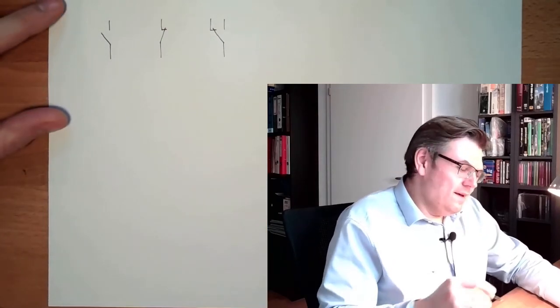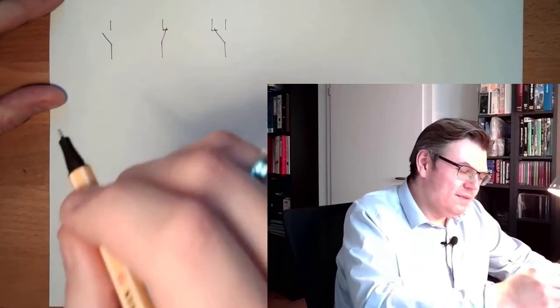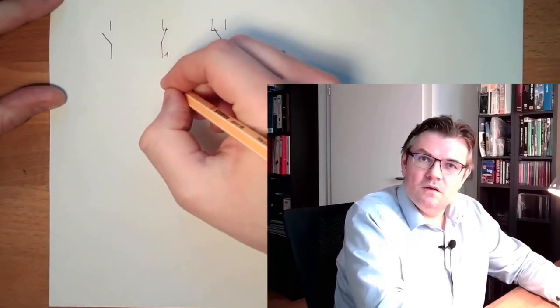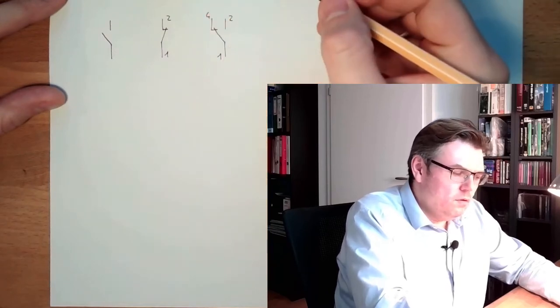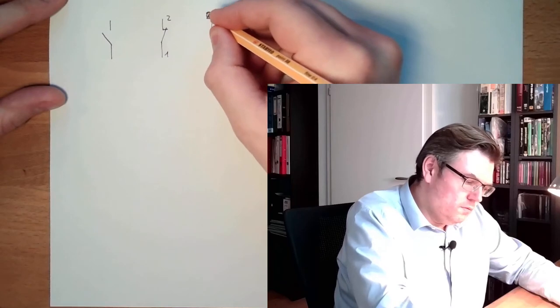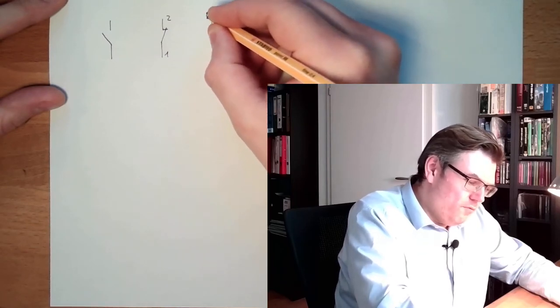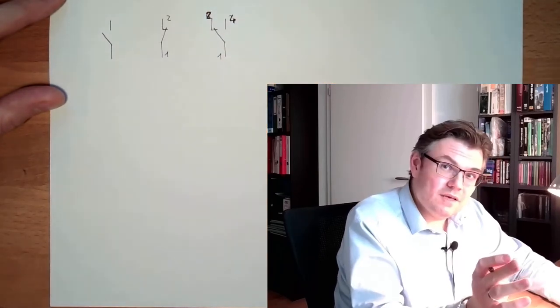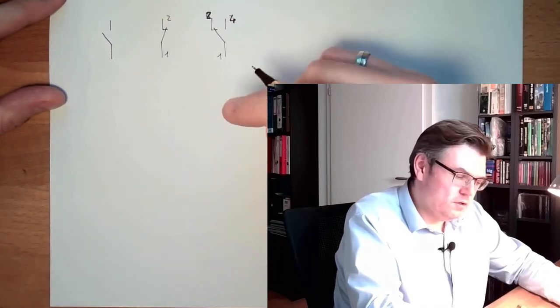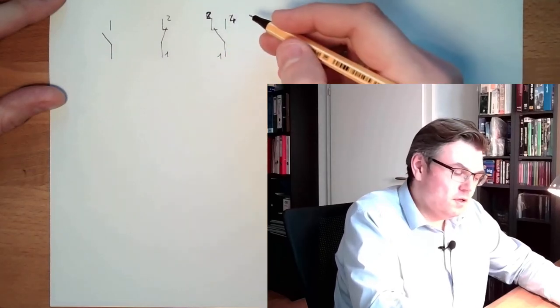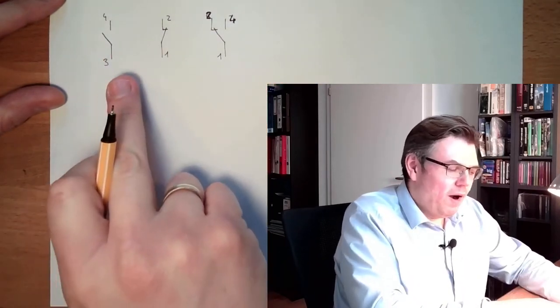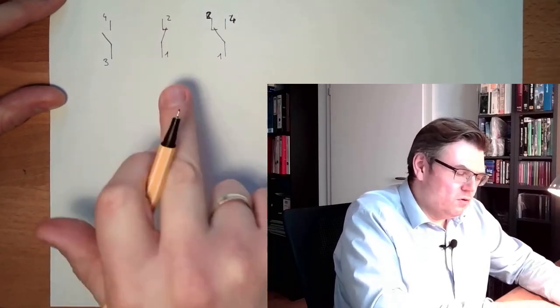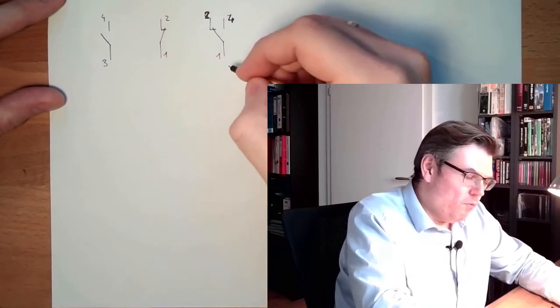So where is the difference? It's like valve symbols — like a way valve. We have almost the same numbering scheme. This is the connection where the power is coming to, and this is the working element. Here we have one, two, and four — just like the way valve connection: one connection where the power is, and two working connections. Here we usually draw it four and three to mark these special contacts.